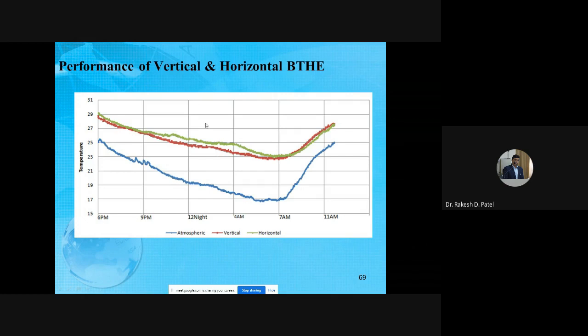Now, this is a comparison result of performance of vertical as well as the horizontal heat exchanger. Many researchers say the horizontal heat exchanger is very convenient for air conditioning purpose. Some researchers say vertical heat exchanger is very convenient for air conditioning purpose. So here I compare both heat exchangers at performance level. The blue color line shows the atmospheric conditions, obviously as per the graph the winter conditions, and the green color line shows the horizontal heat exchanger performance, and the red color line shows the vertical heat exchanger.